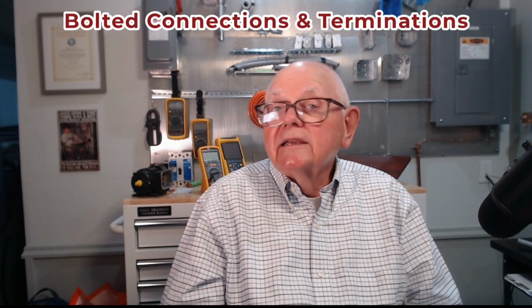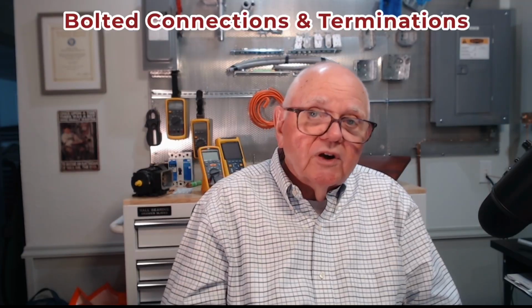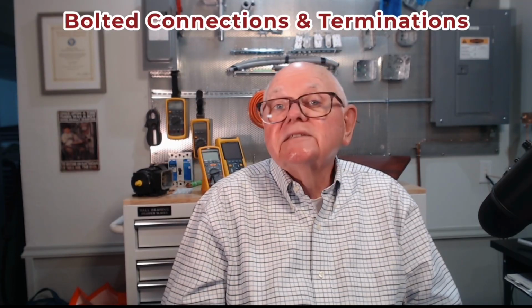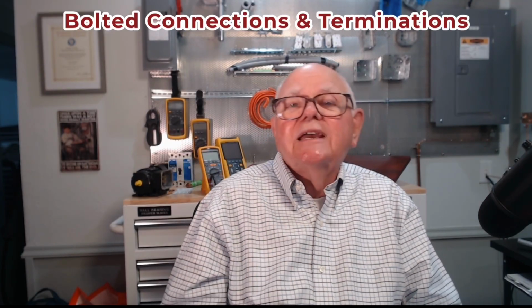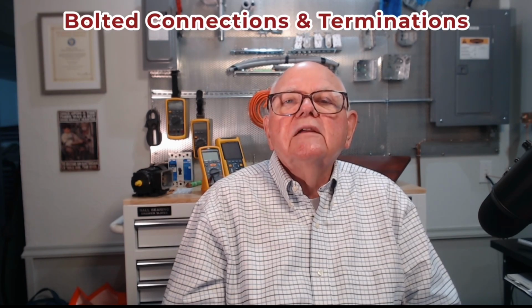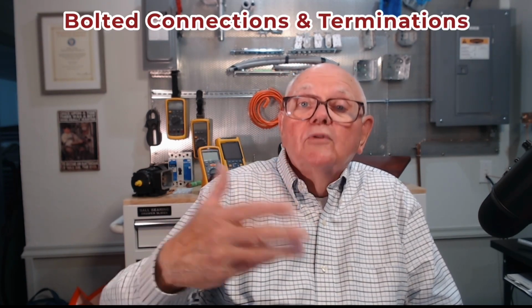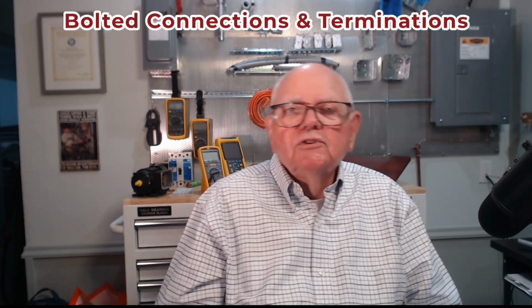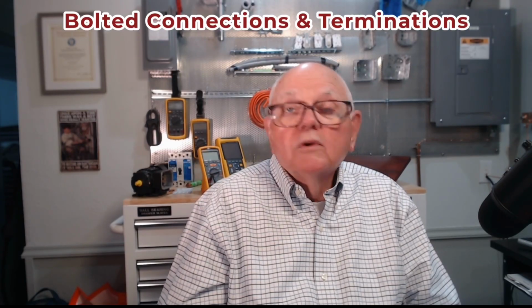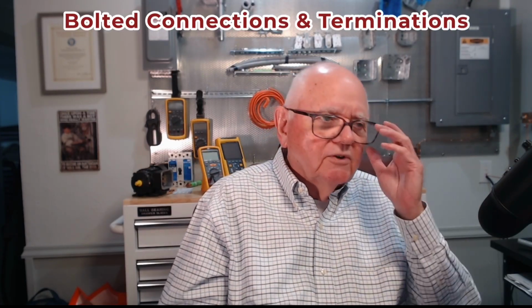Now, in cases where you don't know what those torque values are, the NFPA 70B standard has 3 separate tables in it based on the type of bolt that you have as to how tight you should make that up. You know, how many foot-pounds you should apply to it.